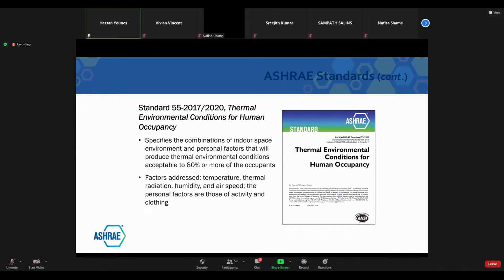But there are also other things you need to look at, like thermal radiation. If there's someone sitting next to a window and there's a lot of sun radiation, he might not be very comfortable. So you need to look at that as well. Humidity, airspeed. You can probably tolerate higher temperatures with higher airspeed. So you can increase maybe the set point from 23 to 25 or 25.5, still be comfortable if you have higher airspeed, and probably reduce your energy consumption because now you're operating at a higher temperature. The personal factors are those of activity and clothing.